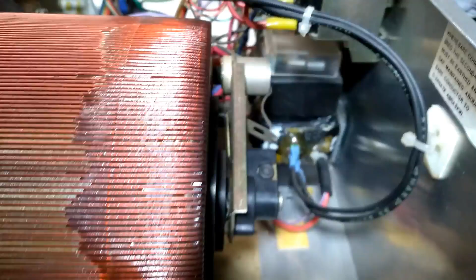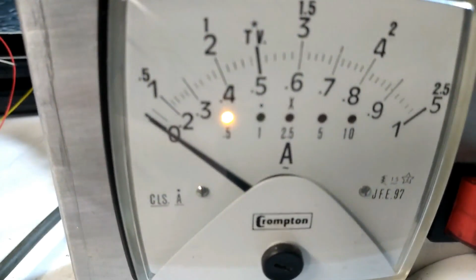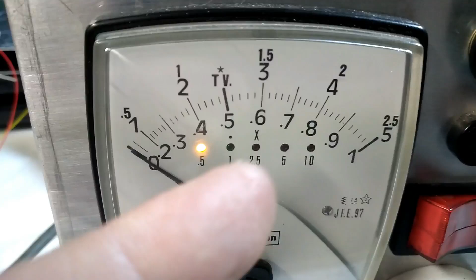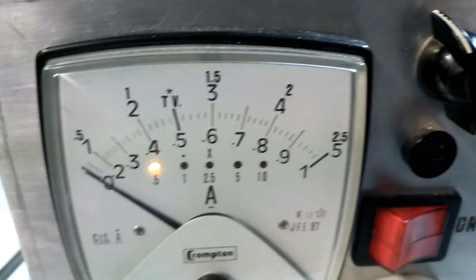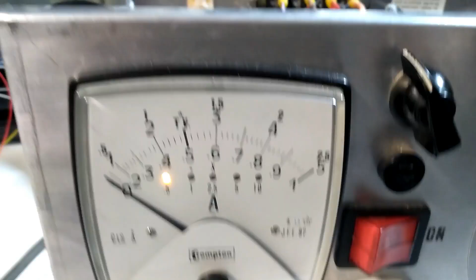So the primaries are the scales. You have one winding, one coil, for the 0.5 of an amp scale. Then you've got another winding for the 1 amp, and then 2.5 amps and 5 amps, and then another winding for the 10 amps. So that's how it's been made.